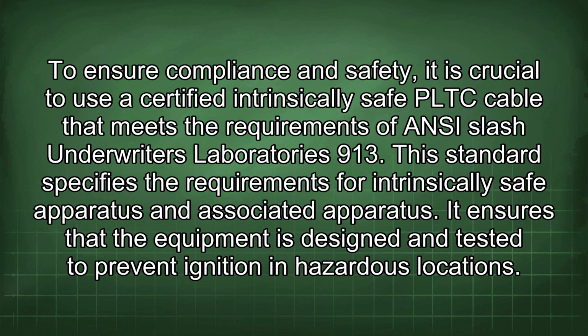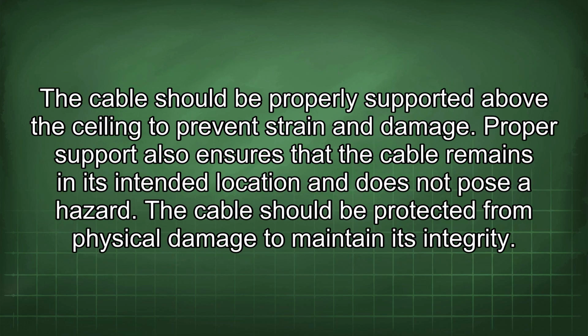To ensure compliance and safety, it is crucial to use a certified intrinsically safe PLTC cable that meets the requirements of ANSI/Underwriters Laboratories 913. This standard specifies the requirements for intrinsically safe apparatus and associated apparatus. It ensures that the equipment is designed and tested to prevent ignition in hazardous locations. The cable should be properly supported above the ceiling to prevent strain and damage. Proper support also ensures that the cable remains in its intended location and does not pose a hazard. The cable should be protected from physical damage to maintain its integrity.